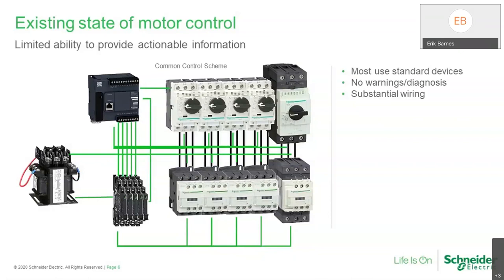We have overload protection, which, if there's too much current being drawn by the motor for an extended period of time, will trip. That could be in the form of an overload relay. In this case, we're showing a manual motor controller ahead of the contactor. Those functions have stayed the same. The designs have gotten smaller, more efficient, with less coil consumption in the contactor. But functionally, they really remain the same.